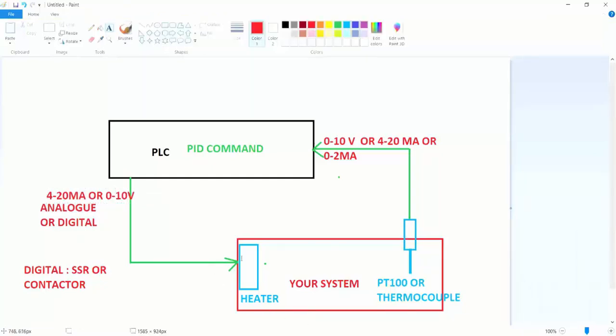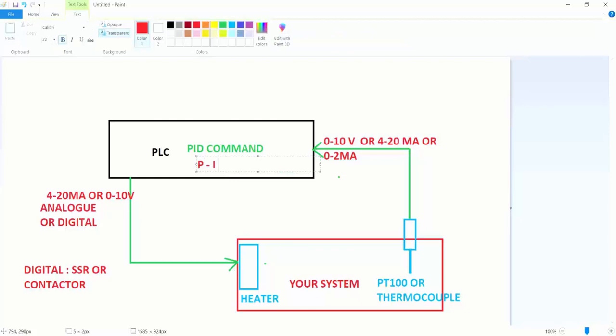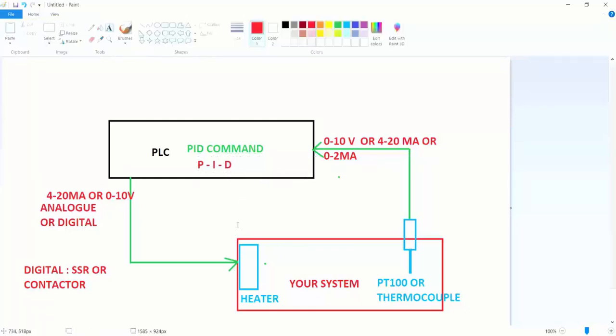In our real example today, we control with a heater, and the heater is digital — on/off — and we will use a contactor. If you want, sometimes you must use an SSR, and sometimes a contactor, depending on your system. With this system we use PID control, and by adjusting the P, I, and D parameters we will control our system very well with only one contactor.